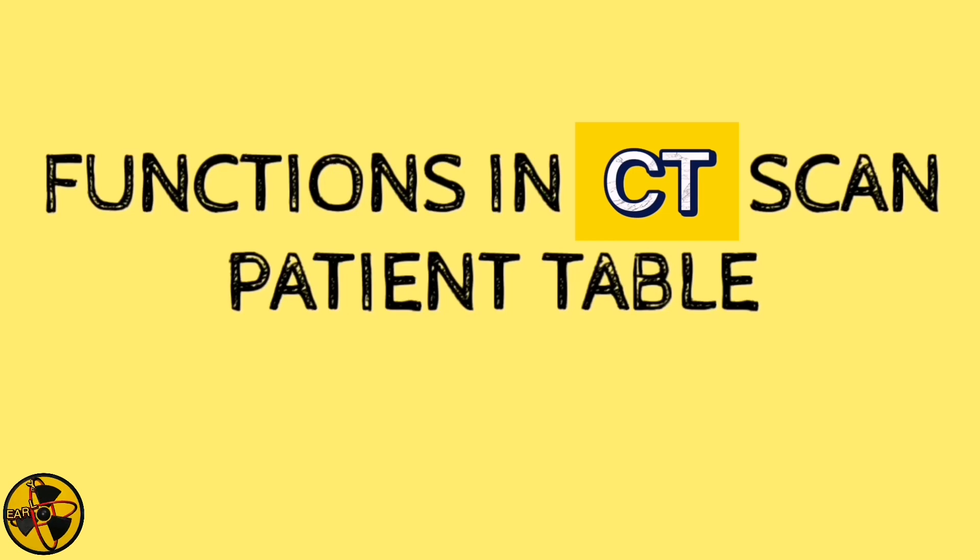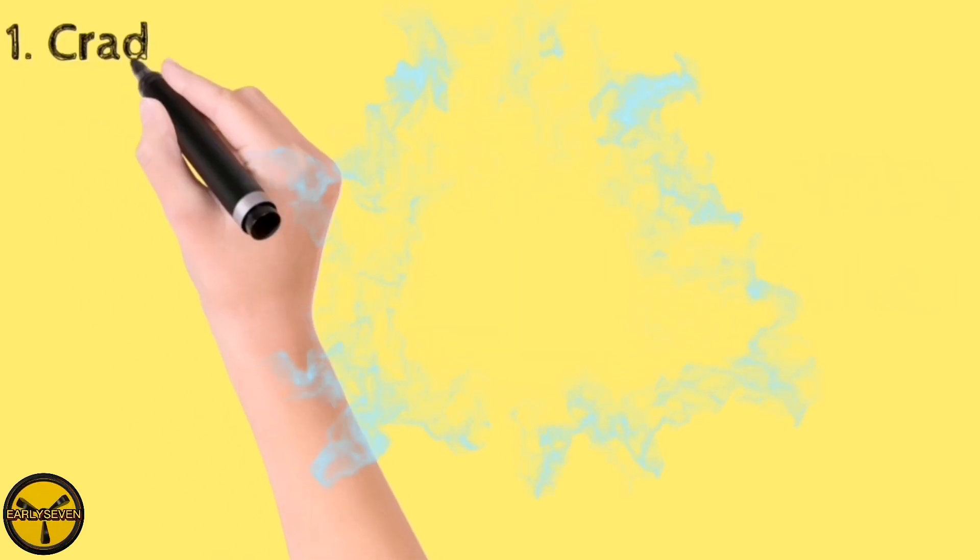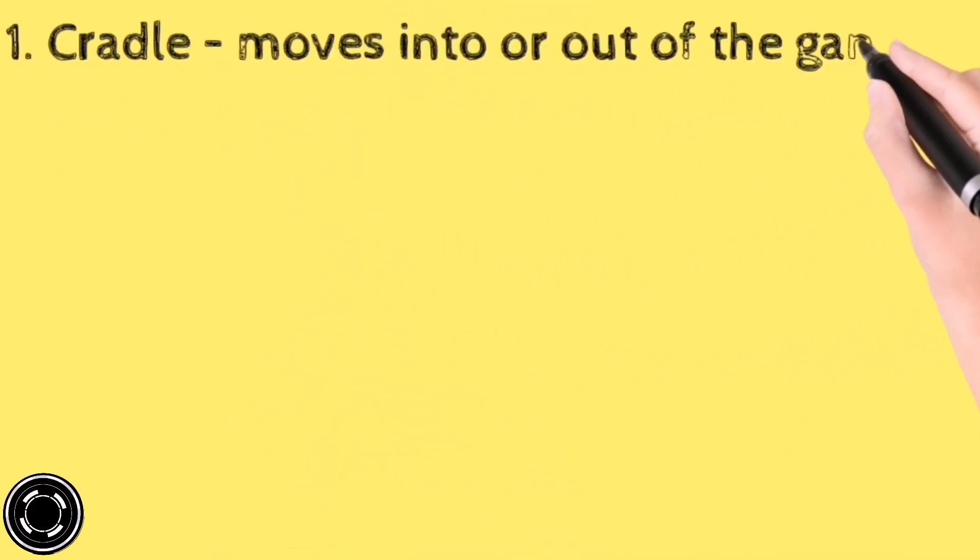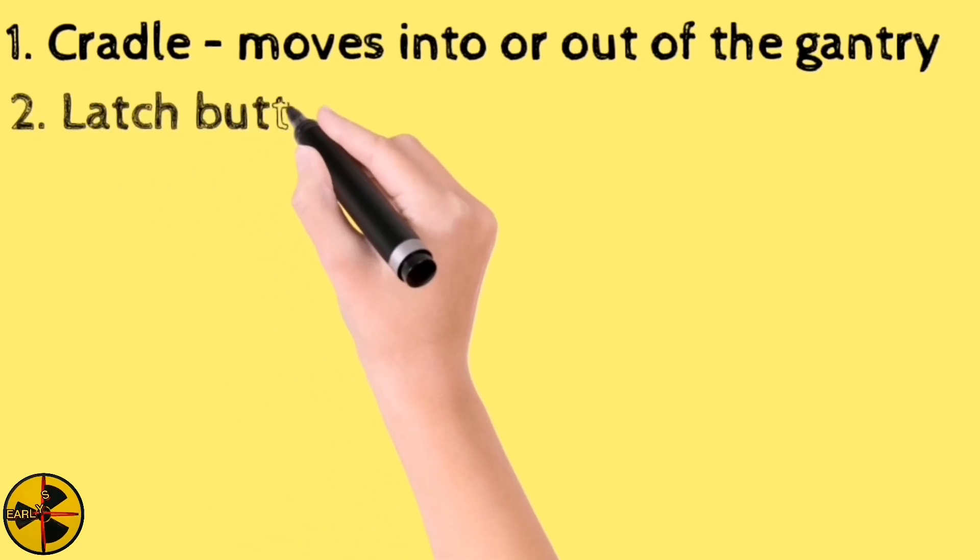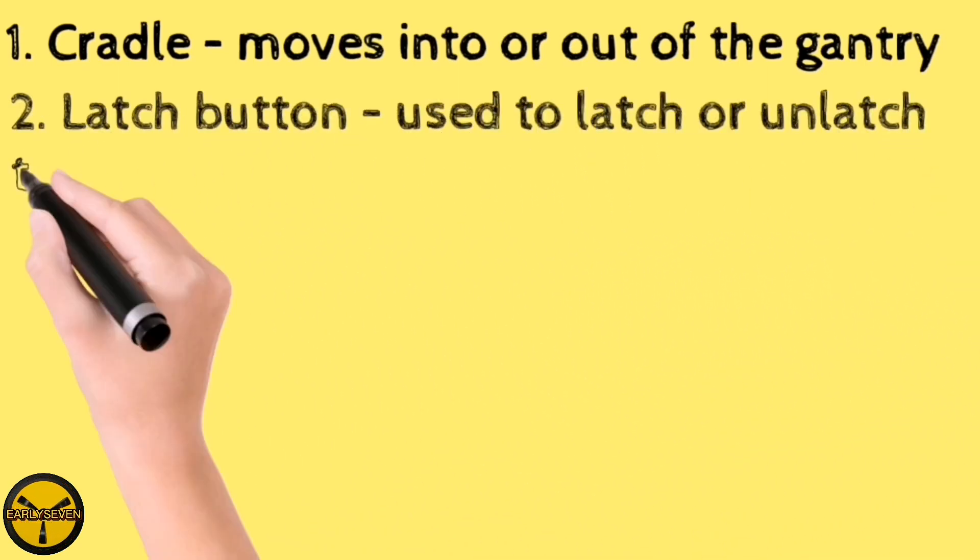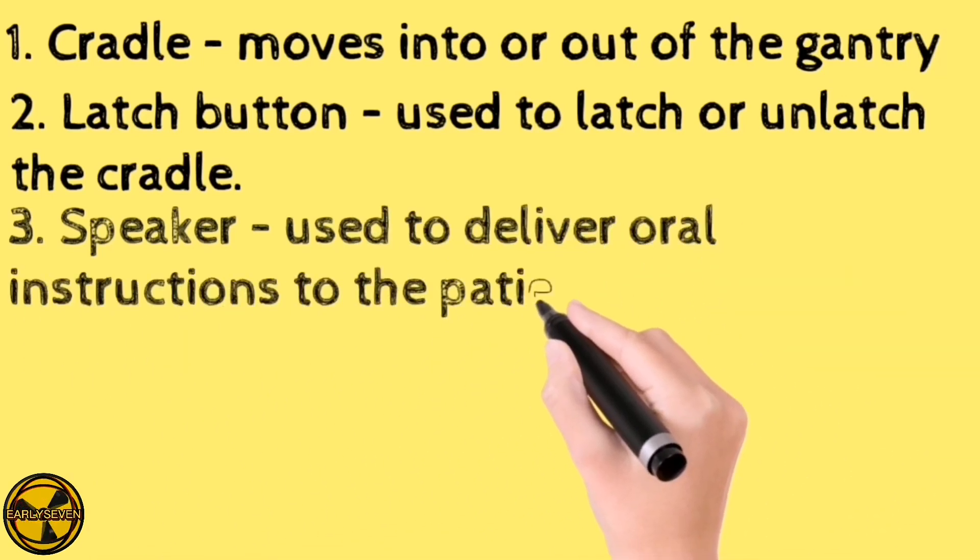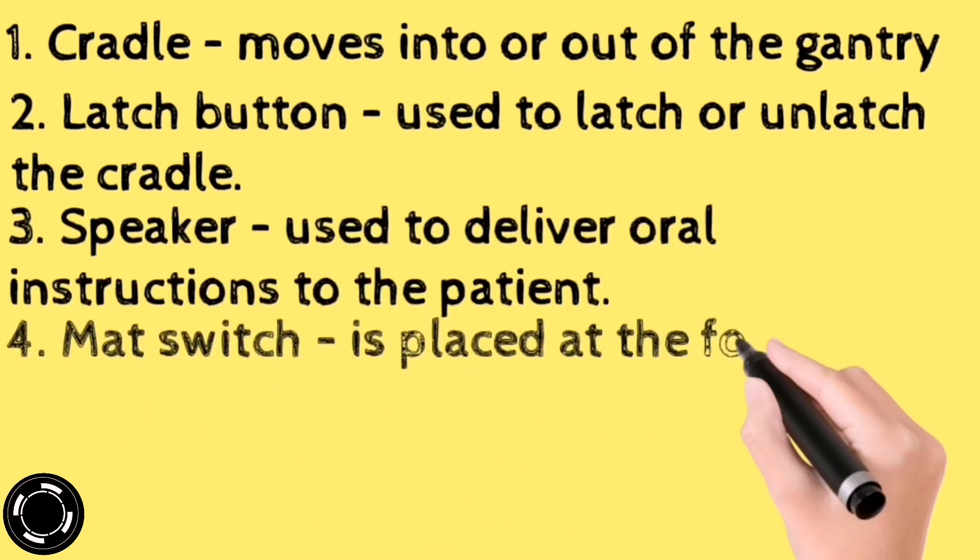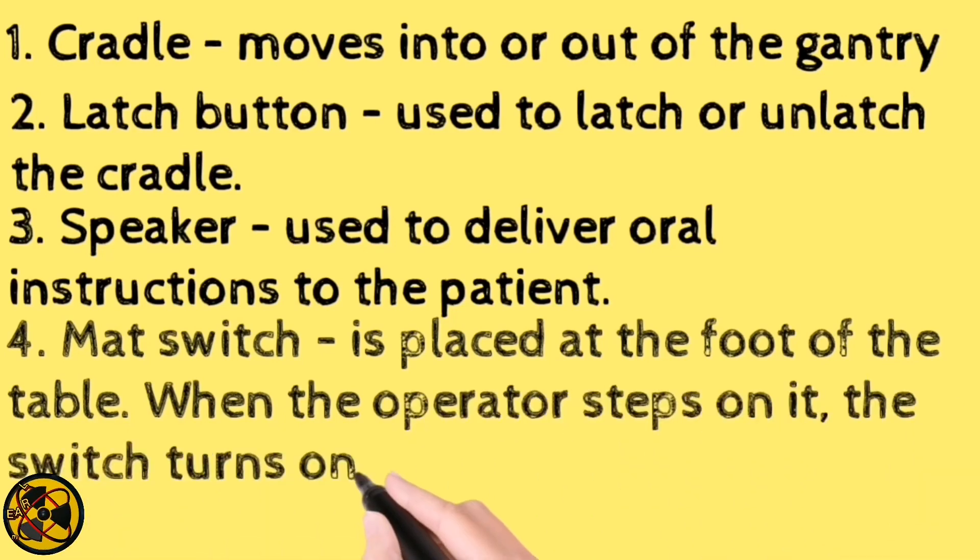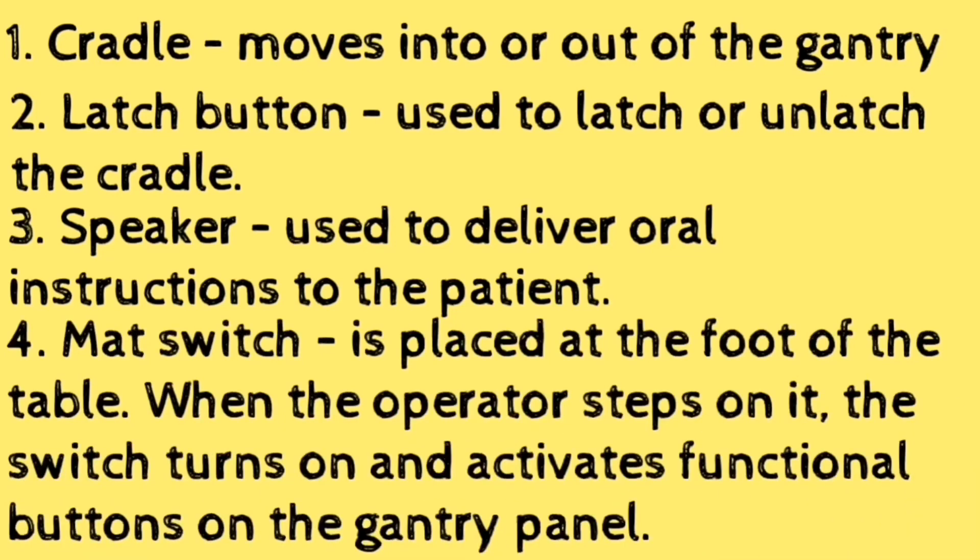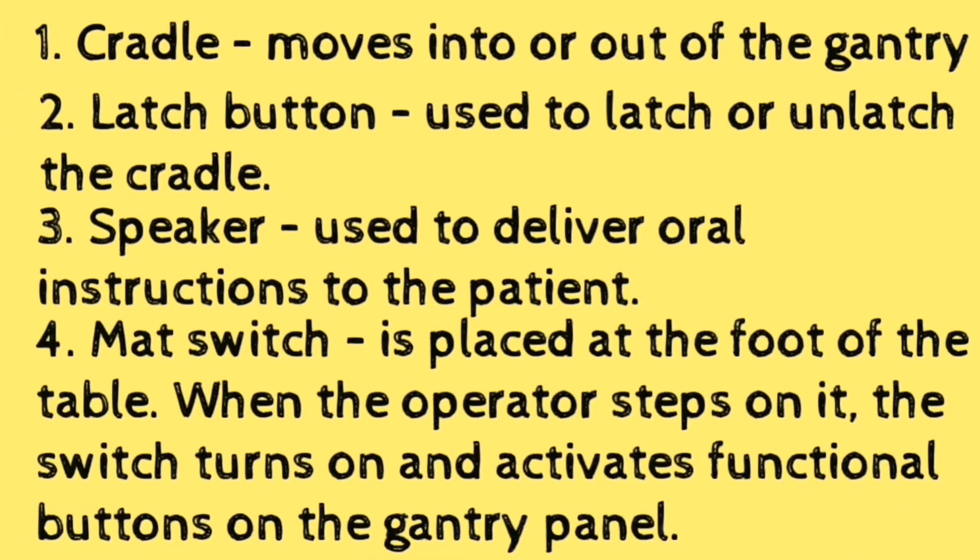What are the functions in a CT scan patient's table? The cradle moves into or out of the gantry. The latch button is used to latch or unlatch the cradle. Next is the speaker, which is used to deliver oral instructions to the patient. In the mat switch, that is placed at the foot of the table. When the operator steps on it, the switch turns on and activates functional buttons on the gantry panel.